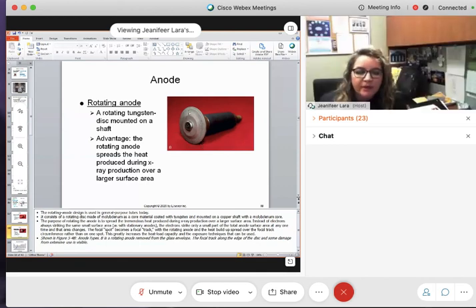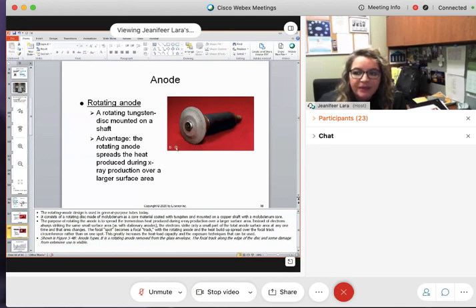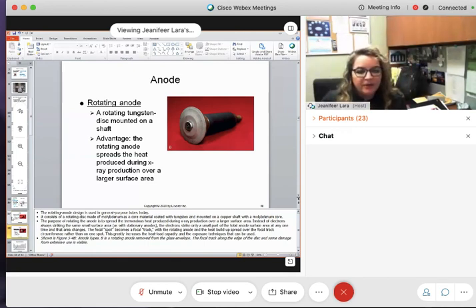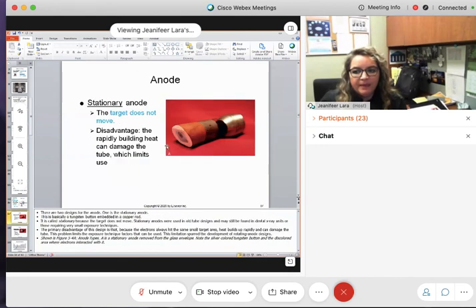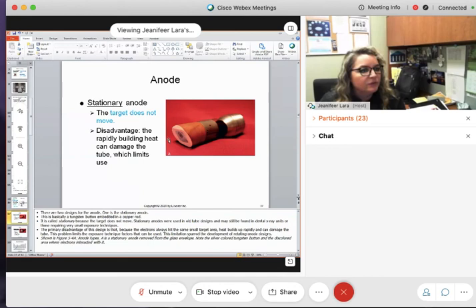That's going to eventually be called a focal track. The disc is constantly rotating and the electrons are bombarding different parts of it, so a lot of the heat is being dissipated — it's being moved around. As opposed to the stationary anode, where it's just hitting one spot and the heat has nowhere to go.